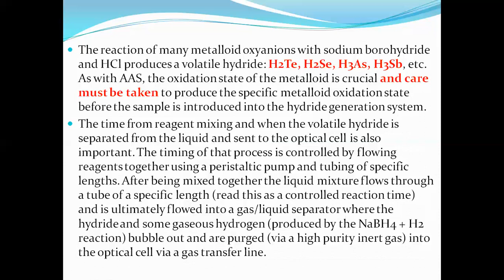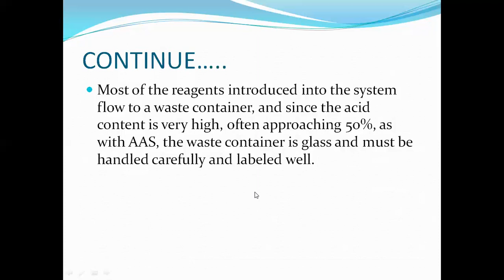The time of reagent mixing is also very important, and this is controlled by flowing reagents together using a peristaltic pump and tubing of specific length. After being mixed together, the liquid mixture flows through a tube of specific length and is ultimately flowed into a gas liquid separator, where the hydride and some gaseous hydrogen bubble out and are purged into the optical cell. Most of the reagents introduced into the system flow to a waste container, and since the acid content is very high, often approaching 50%, as with AAS, the waste container is glass and must be handled carefully and labeled well.